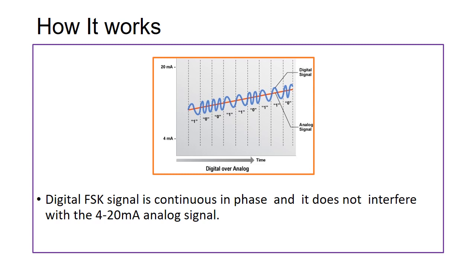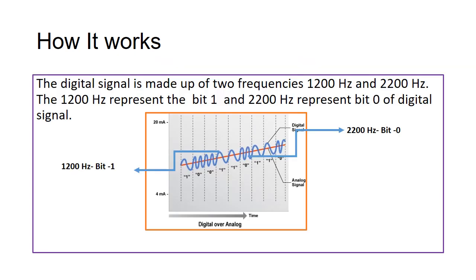HART protocol works by using frequency shift keying (FSK) standard to superimpose digital signals onto the 4 to 20 milliampere analog signal. The digital FSK signal is continuous in phase and does not interfere with the 4 to 20 milliampere analog signal. The digital signal superimposed on the analog signal is made up of two frequencies: 1200 Hz representing bit 1, and 2200 Hz representing bit 0.